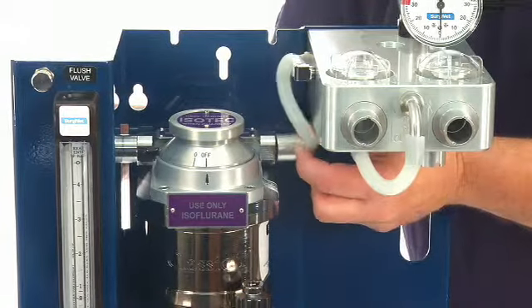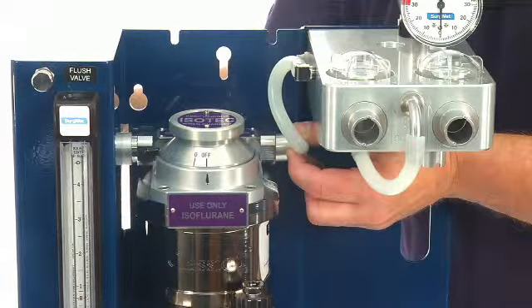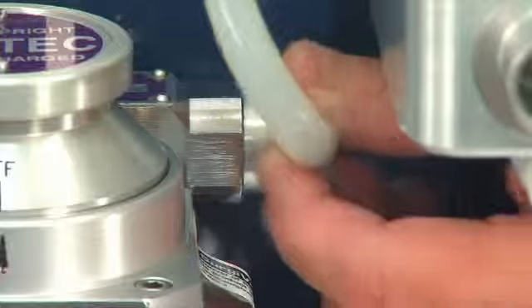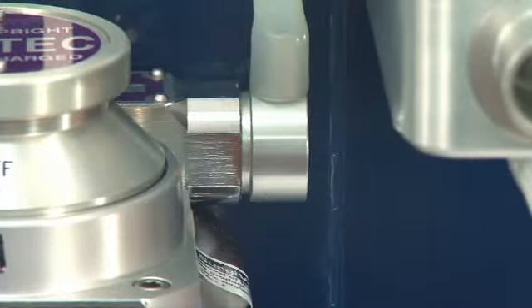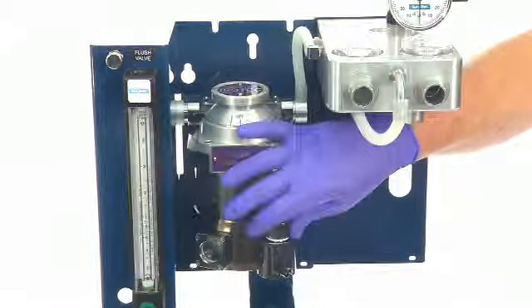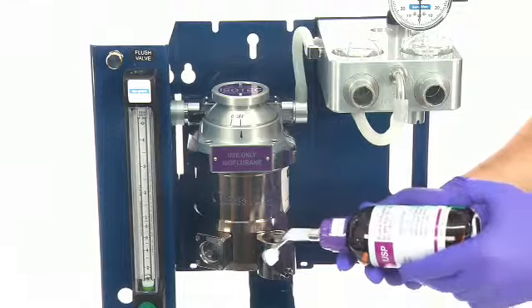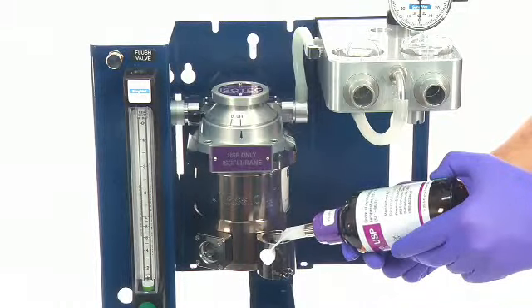Secure the end caps to the vaporizer. The tapered end caps will fit securely into the vaporizer. Tighten them gently by twisting upward into place. Once a vaporizer is secured to the anesthesia machine, it can be filled with the appropriate anesthetic agent.